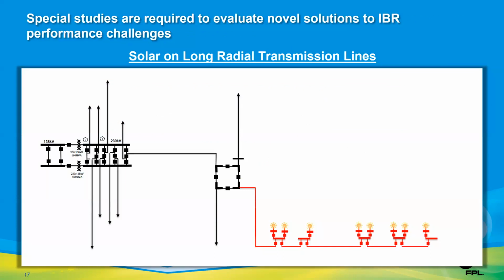So I mentioned earlier that we've been seeing requests for solar in remote areas of our territory. In this particular case, we have 8 PV plants proposing to interconnect to a long radial line. Once again, there were no issues when we looked at this in load flow, short circuit, or transient stability analysis. However, in EMT analysis, we saw oscillations for normally cleared faults. We also had events on adjacent lines that led to tripping of these PV plants. We would have missed some of these performance issues if we didn't run the EMT analysis.